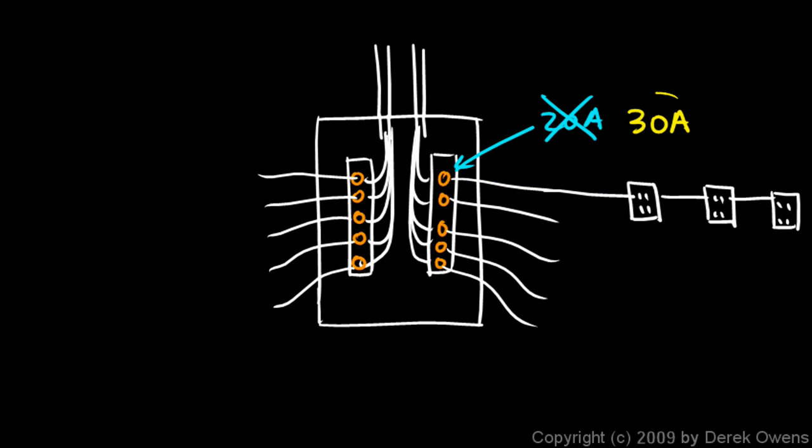The reason there was a 20-amp fuse here was because this wire isn't supposed to have more than 20 amps in it, and if you replace the 20-amp fuse with a 30-amp fuse, then you're allowing more electricity to flow through this wire than it was designed to handle, and that's the kind of thing that would typically start a fire, people replacing the fuse with one that's the wrong size or the wrong amperage and allowing too much electricity to flow and too much heat to be generated, and a fire gets started.